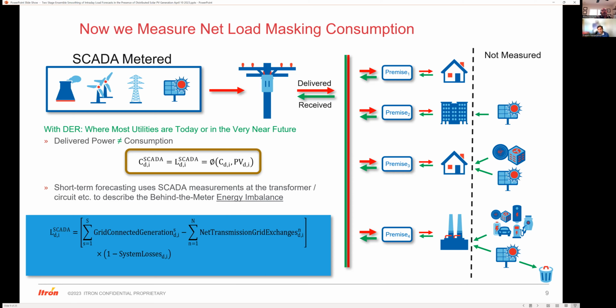They have to black out the neighborhoods. So what they want to do is still incent people to put excess capacity in, but give them dynamic operating envelopes. Some days they'll say, you got to turn your solar inverter off because there isn't enough room to backflow. Other days, you could generate 10 kW and push all of it onto the grid because the transformer will have capacity for it.